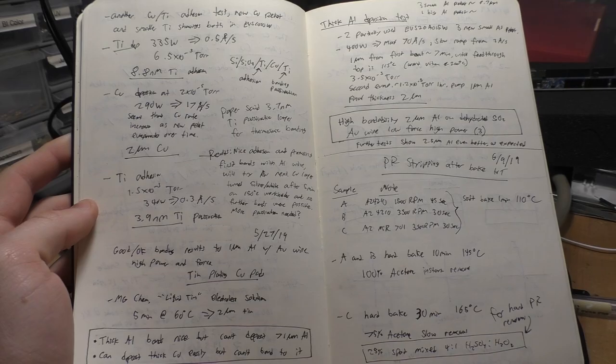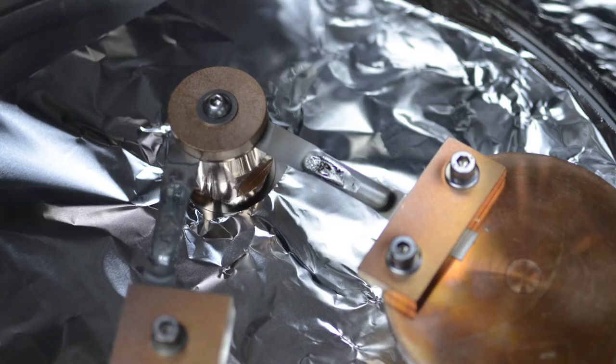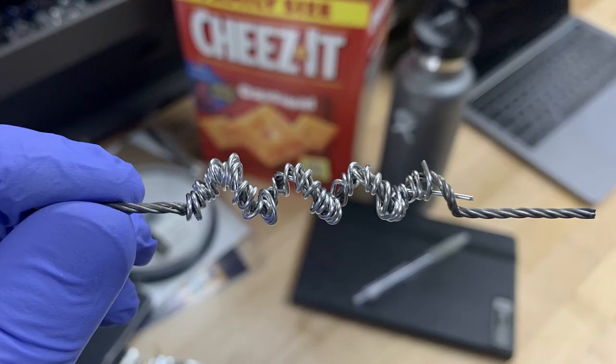I've got pages of notes from when I was trying to figure out how to beat this. It turns out that the metal adhesion is really difficult to get right. Thoroughly cleaning the substrate first with things like piranha etch, acetone, isopropyl alcohol, and water seem to help quite a lot, as well as dehydrating the surface under high temperature. Aside from that, doing the depositions of aluminum or whatever metal at the lowest vacuum possible to achieve the highest level of cleanliness in there really seems to help. I start the depositions around 7 times 10 to the negative 7 torr. They always end a lot higher than that because of outgassing, but starting at lower seems to help. And high deposition rates also allow for a lower probability of gas to be incorporated into the film as it's deposited, and that also leads to better adhesion.